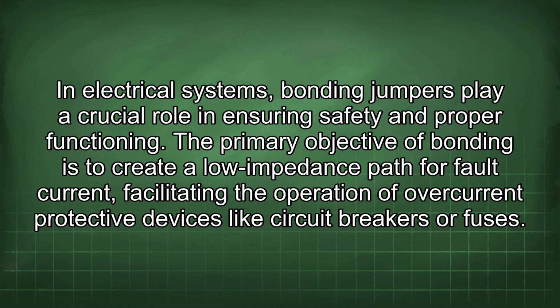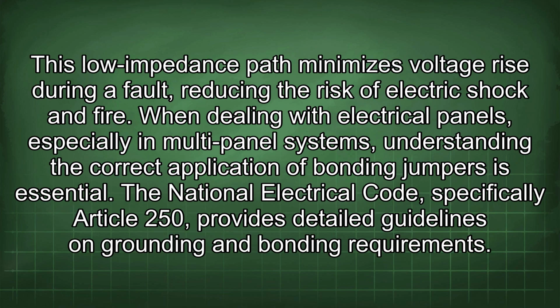In electrical systems, bonding jumpers play a crucial role in ensuring safety and proper functioning. The primary objective of bonding is to create a low-impedance path for fault current, facilitating the operation of overcurrent protective devices like circuit breakers or fuses. This low-impedance path minimizes voltage rise during a fault, reducing the risk of electric shock and fire. When dealing with electrical panels, especially in multi-panel systems, understanding the correct application of bonding jumpers is essential. The National Electrical Code, specifically Article 250, provides detailed guidelines on grounding and bonding requirements.